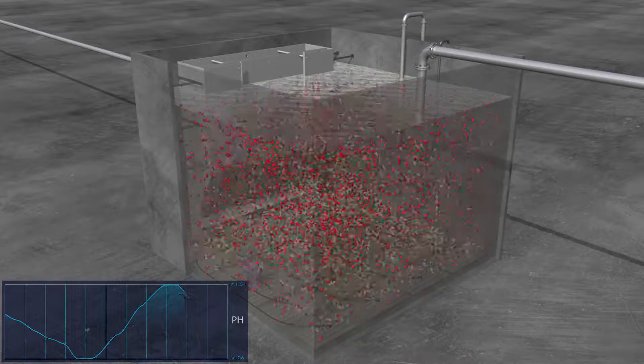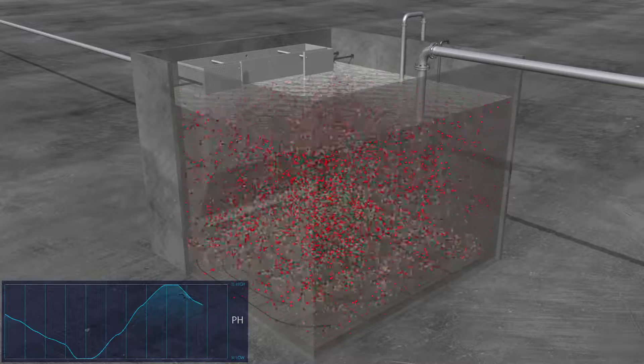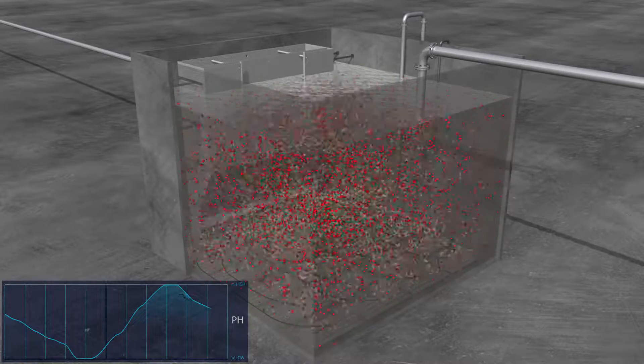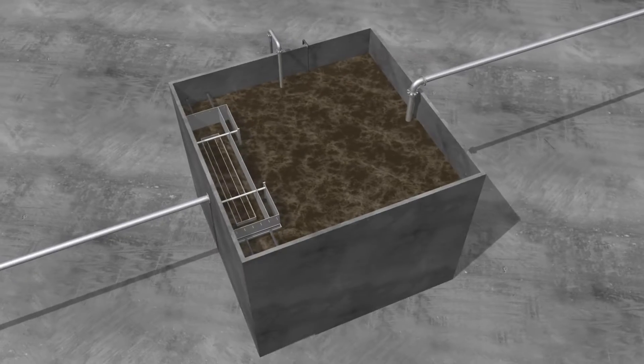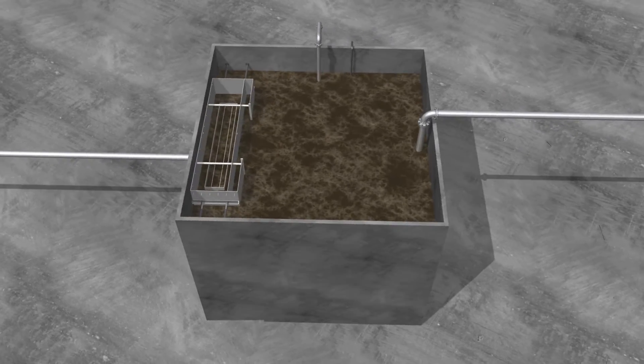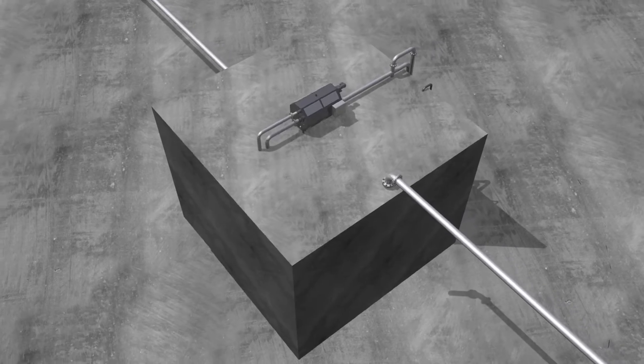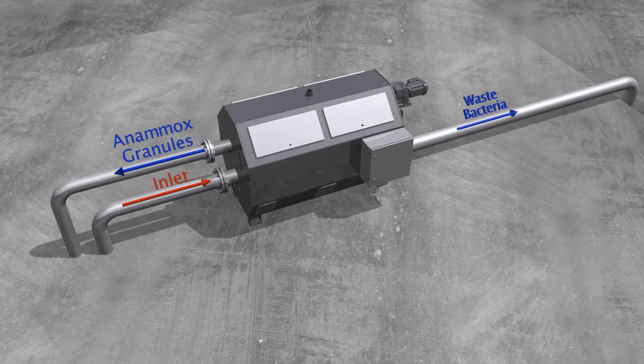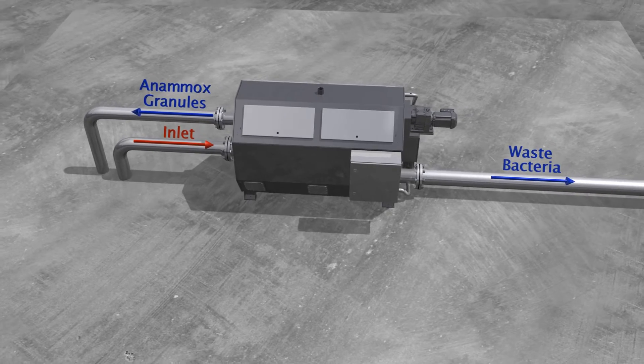The Anammox granular bacteria are a slow-growing bacteria. Due to this, care must be taken to keep them inside the reactor. This is accomplished in two ways. First, when wasting is required by the process, the reactor contents are pumped to a micro screen which will separate the Anammox granules from the other bulk suspended growth bacteria.